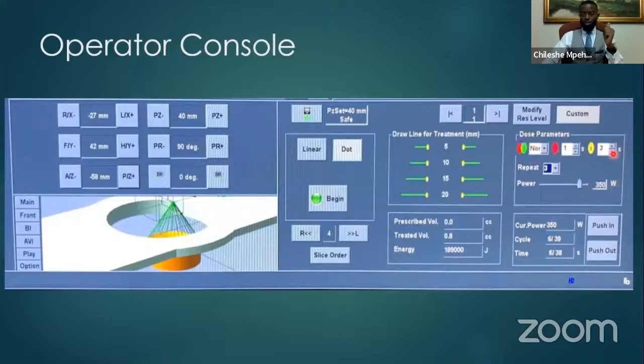When we look at here, we've got a sonication and a rest period. So when I say sonication, I mean treatment, as in to sonicate, as in to give the ultrasound energy. So I'm going to be using that term from now. So when we say we sonicate for 1 second, that's the equivalent of giving the patient 1 second of ultrasound energy at that focal point, and then we rest the patient for 3 seconds. All right, so that is to make sure that that point is heating up. However, there's not a high level of energy transmission to the rest of the uterus, which would be dangerous if we overheated the uterus to the adjacent structures.